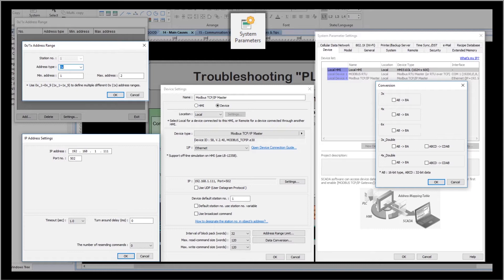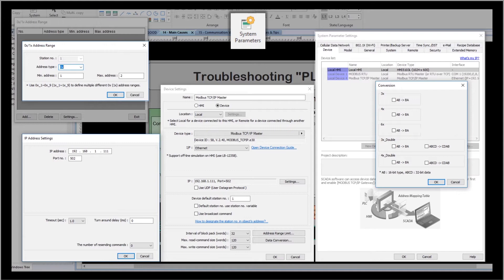For example in Modbus by default from our HMI's if you try to read an output bit that's 0x the HMI will automatically read a group of 16 bits at a time and you may not have 16 bits configured in consecutive order in the PLC. In that case you can set an address range limit if you want to avoid reading memory areas that aren't configured. So this is an example of something that you should check and these sorts of parameters again vary widely by the PLC or controller.